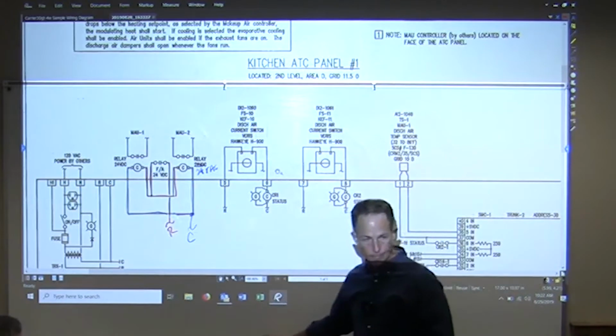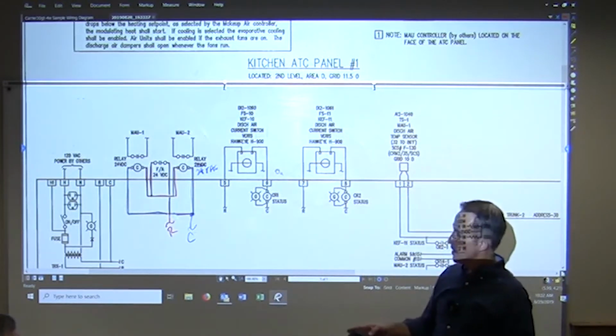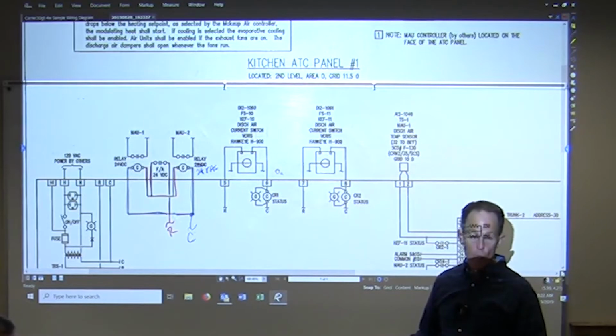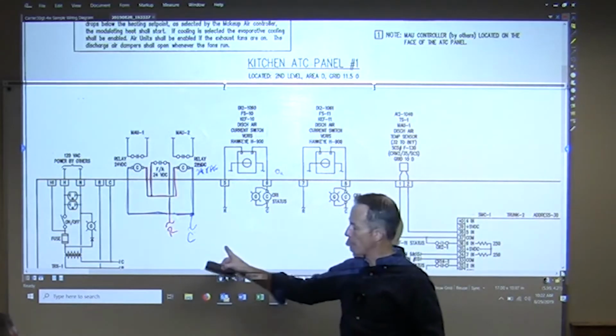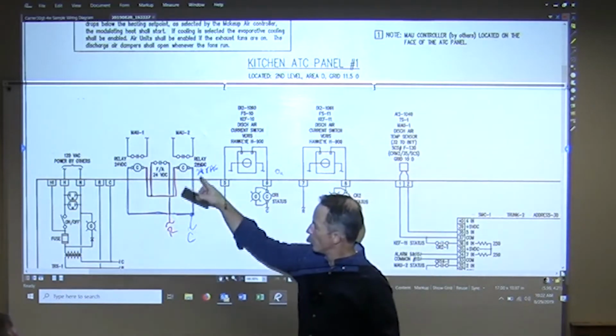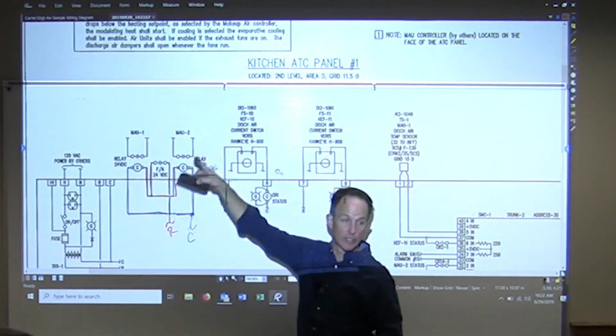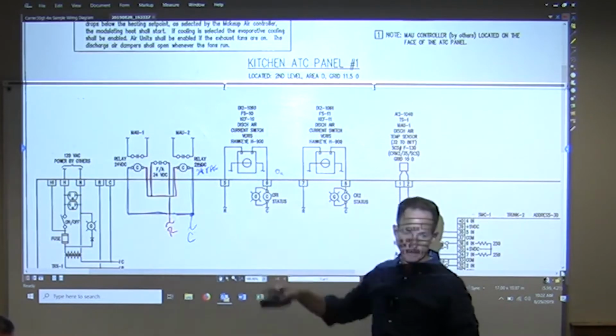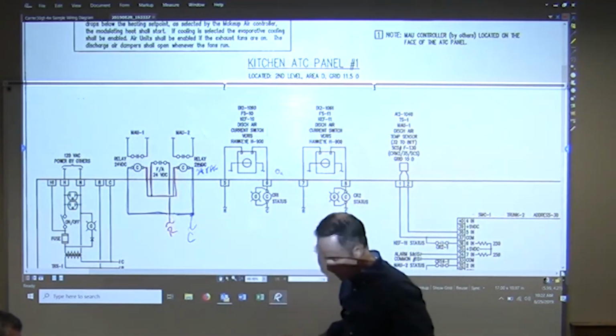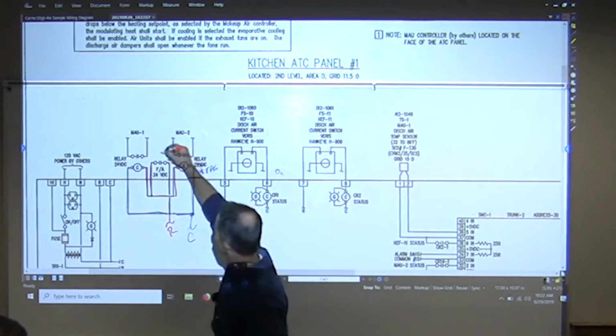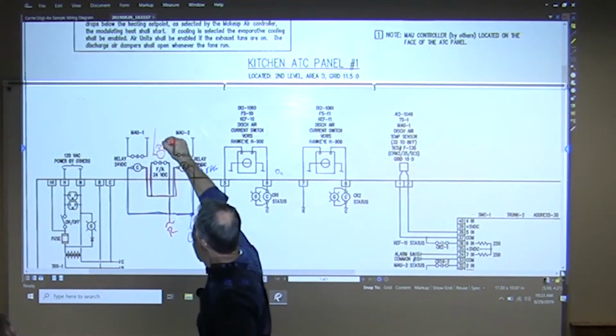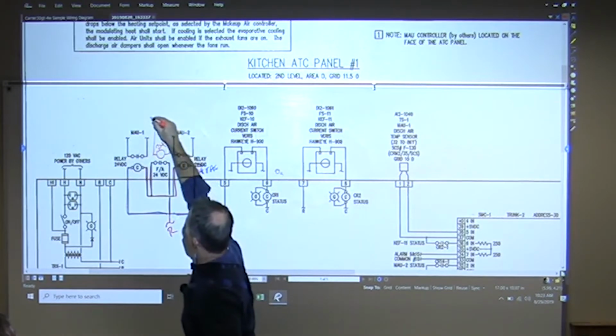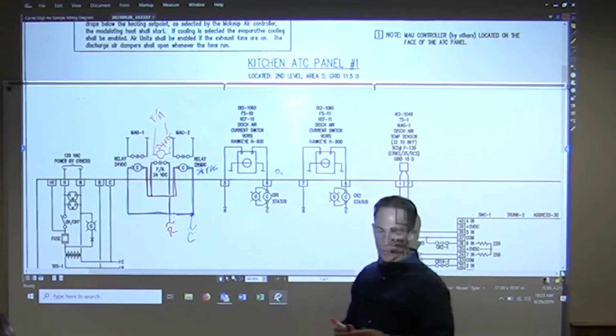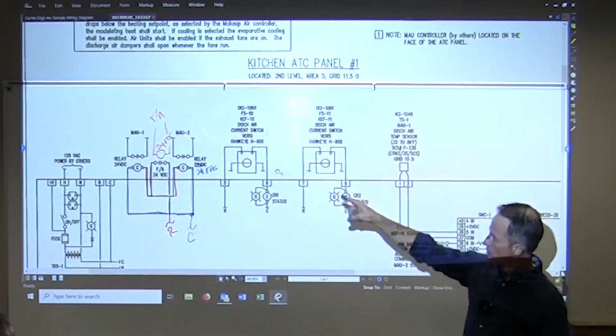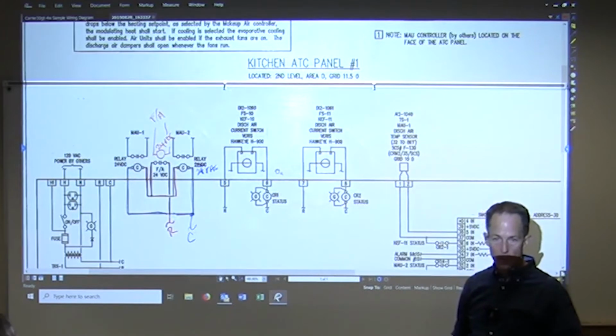Okay. And that would have to be something fed from the fire alarm system, or if it was just powered off the unit, it would never shut the fans off. Right. So in this case, the way it's drawn now, we've powered it out of our panel. And so this would work because this dry contact is into the units, and they've got some power feeding in and out of our contact. But the fire alarm panel or coil is coming from the fire alarm. Yeah, so you would have a fire alarm relay switch, a coil here, which would be 24 volts DC. That would be your fire alarm. So that would energize, we'd use the contacts from there, and then it would work. Okay, so we fixed that problem.